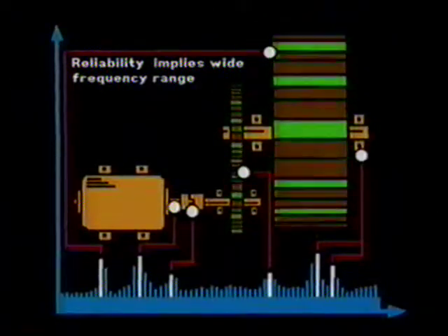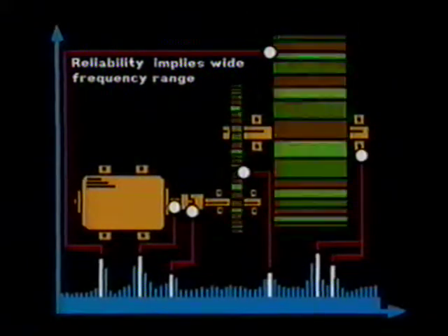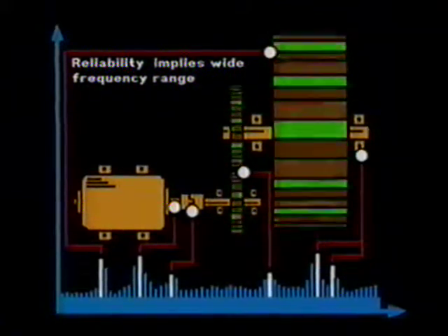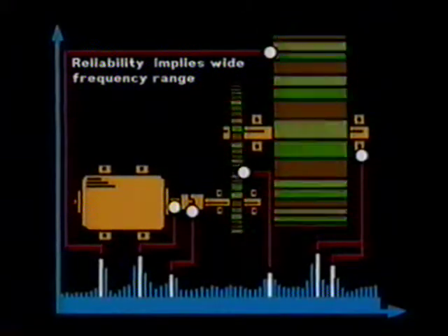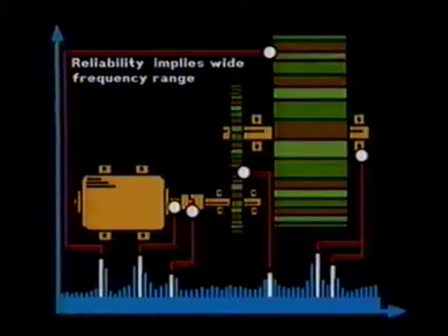You see, most machines contain parts which, if faulty, will produce vibrations over a wide range of frequencies, so to remain versatile and reliable, the transducer must be capable of detecting all the vibrations, whatever their frequency. In the gear-driven fan shown, you can get misalignment, unbalance, bent shaft, oil whirl and eccentricity at low frequencies, gearbox problems at medium frequencies, and rolling element bearing faults at high frequencies.